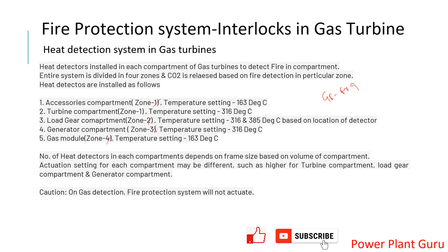There is naturally a temperature difference between the accessory compartment and the turbine compartment, since combustion is happening and the turbine casing is there. That is why we keep different setpoints for temperature sensors in different compartments. For example, in Zone 1, which includes the accessory and turbine compartments, the temperature settings are different: 163°C for the accessory compartment and 316°C for the turbine compartment, since it normally runs at a higher temperature. Similarly, Zone 2 is the load gear compartment, which is also a high-temperature area and has its corresponding setting.